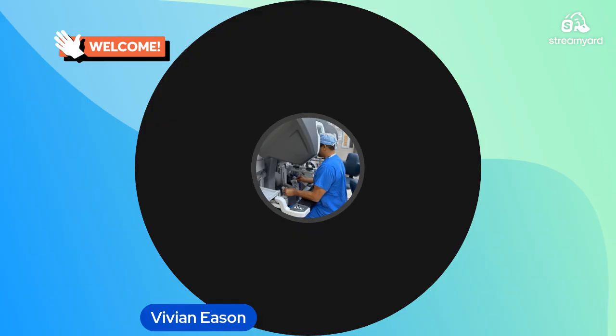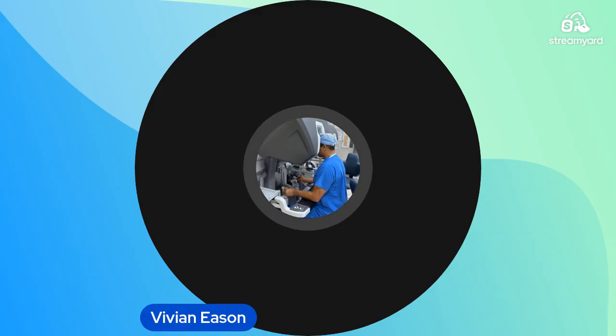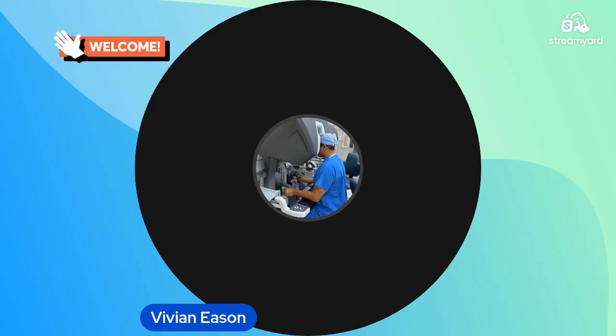Depending on the instrument, the tip may grasp, cut, dissect, suture, or manipulate tissue. For example, robotic instruments may include needle drivers, bipolar forceps, monopolar scissors, graspers, and vessel sealing instruments. Because these instruments are complex, sterile processing professionals must understand that they cannot always be processed exactly like basic open surgical instruments. The manufacturer's instructions for use, or IFU, are extremely important. The IFU provides the cleaning, disassembly, inspection, sterilization, and maintenance instructions.